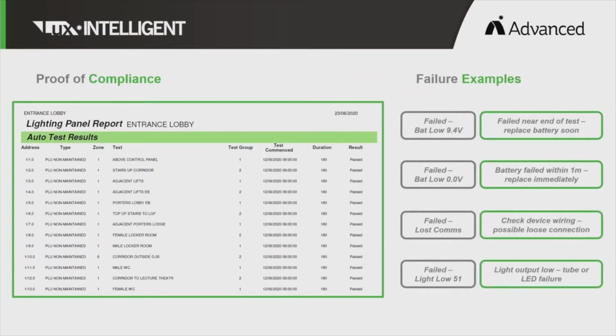Here's an example of an auto test result. It shows you the device address, type, zone, location, test group, when the test commenced, and the test duration, and whether it passed or not. If it doesn't pass, you receive a number of different failure reports, a few of which are shown here as examples.